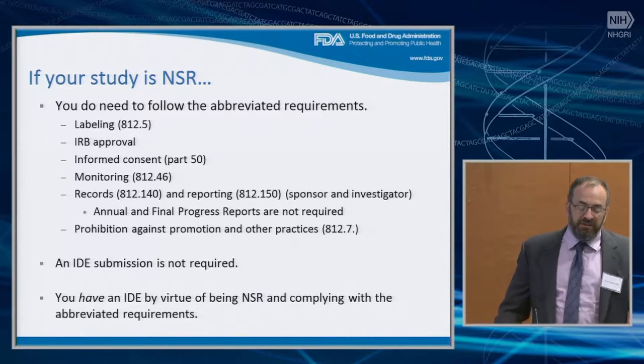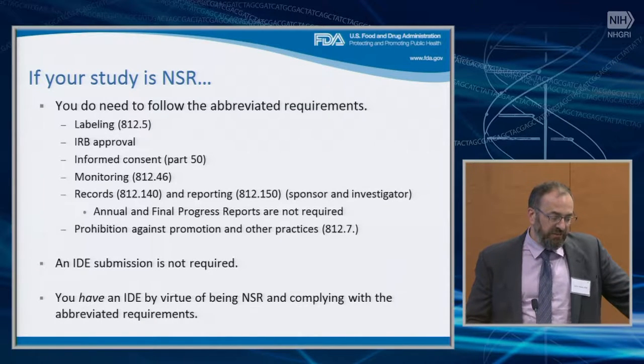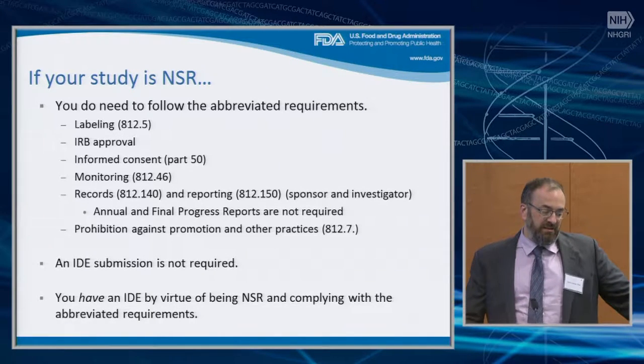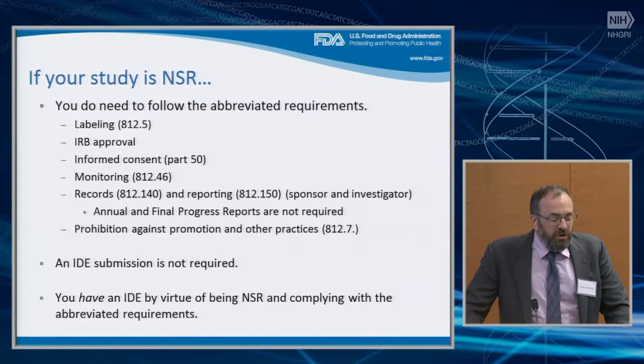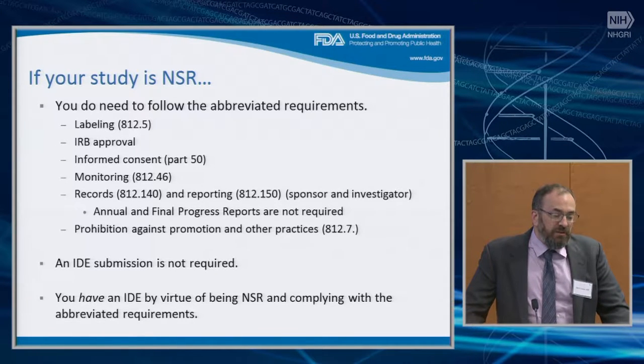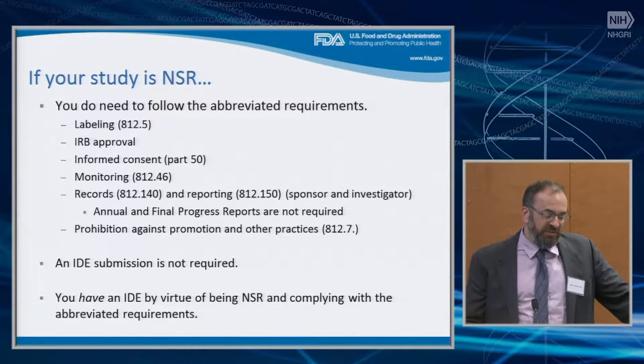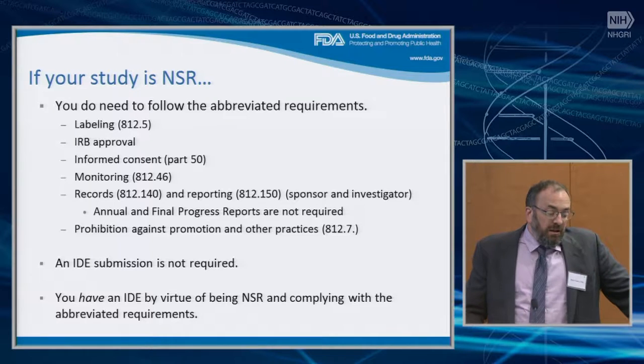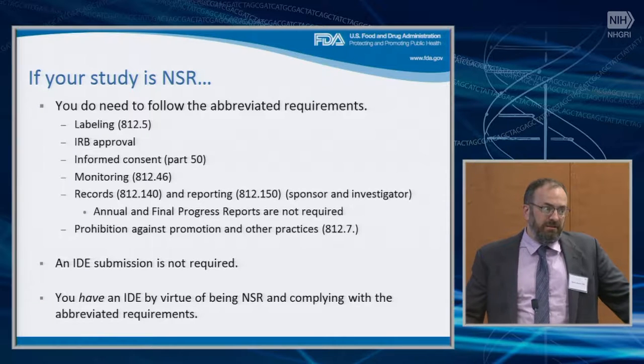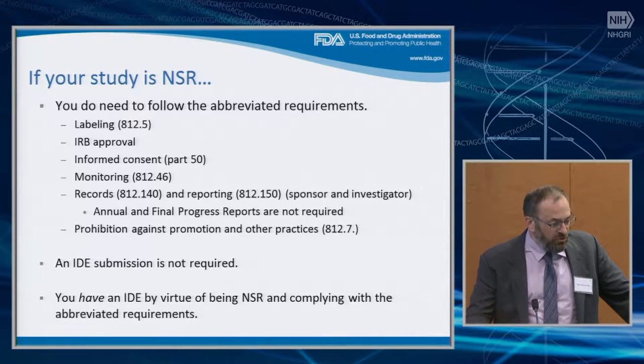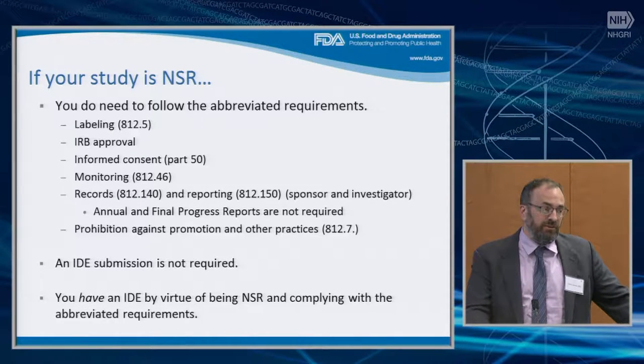If it's non-significant risk, we come back to the abbreviated requirements. A lot of them are things you don't have to send — you don't need an IDE submission, and that's always the big thing people don't want to do. You do need to follow the other abbreviated requirements. Some of them are things you would do anyway, like IRB approval, informed consent, and monitoring in many cases. We do have requirements for records and reporting, but you don't need to send annual and final progress reports. Really, the only thing you'd need to send to us would be any unanticipated adverse events, as those arise.